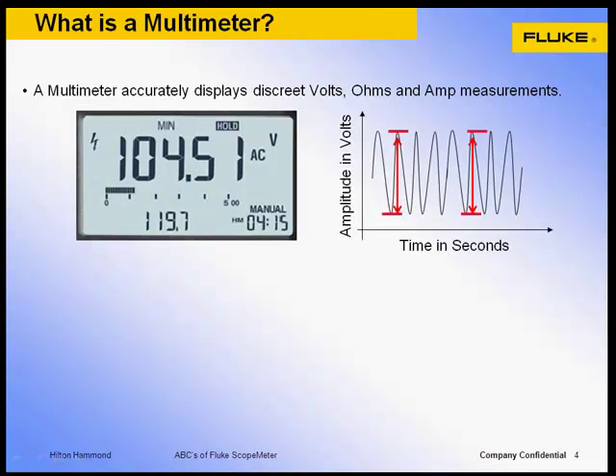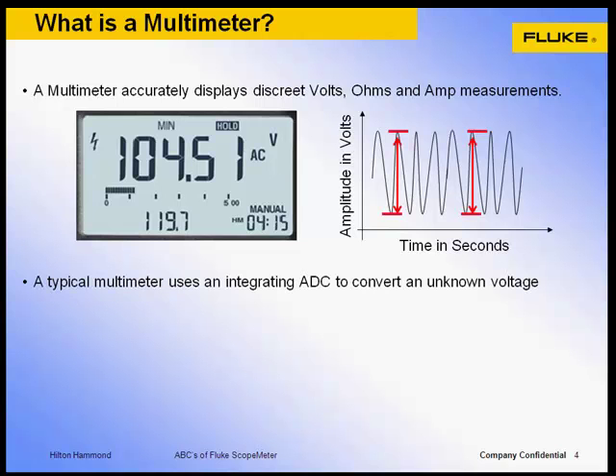Let's start with understanding the basic principles of a multimeter. A typical digital multimeter will use a dual-slope integrating analog-to-digital converter, or ADC. Basically, the ADC works by first applying the unknown input to an integrating capacitor circuit, much like filling up a storage tank with some liquid. The unknown signal is applied to the circuit for an exact known amount of time, usually from milliseconds to as much as a second.